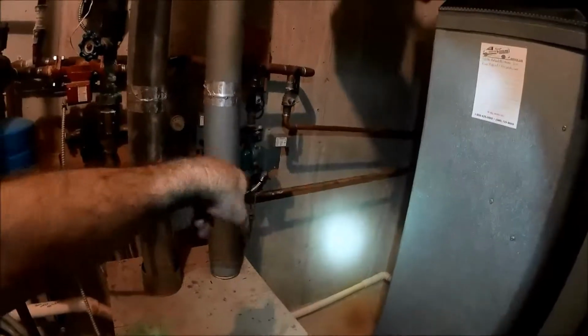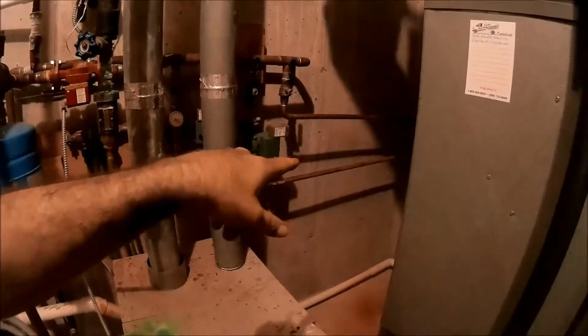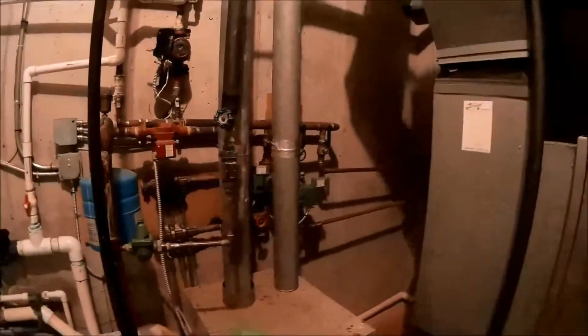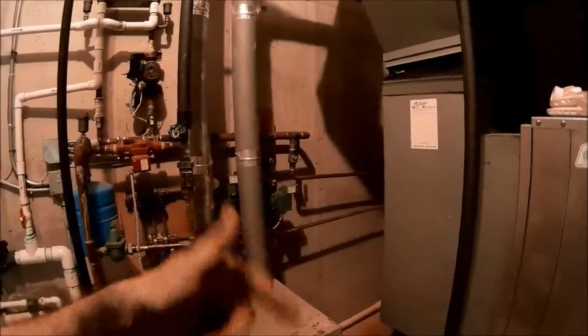But this is coupled up to a boiler. We got a reheat coil for when we need to provide heat, and the dehumidification system in the winter - you're turning on that air conditioner in the winter, that's what a dehumidifier is. And what this does is provide, it's a reheat coil, that's all it is, so it heats that cool air before it hits the space. Also, if it doesn't need dehumidification, it will just turn on the pump, turn on the reheat coil, and heat the space.